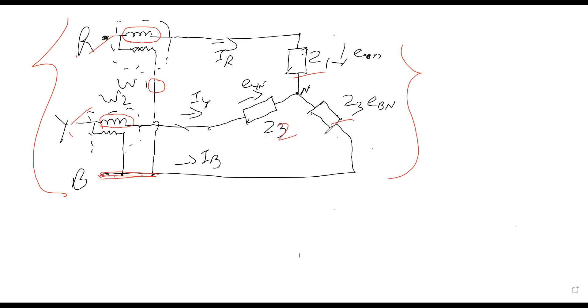The potential coil of each wattmeter is joined on the same line, and the remaining line where these are not connected will be connected to these particular lines. The total instantaneous power absorbed by the three loads, Z1, Z2 and Z3, is equal to the sum of power measured by W1 and W2. This is the actual working of the 2 watt meter: whatever power is absorbed by these three loads is being measured by these two. This is the actual circuit, for star, or you may also convert it to a delta connection.